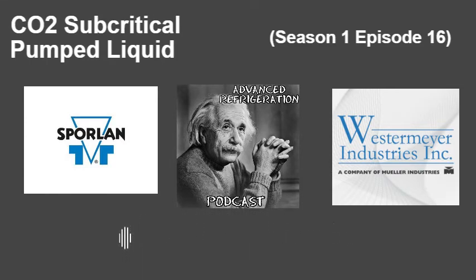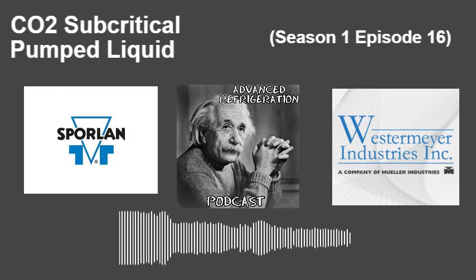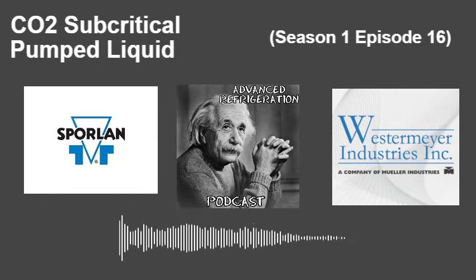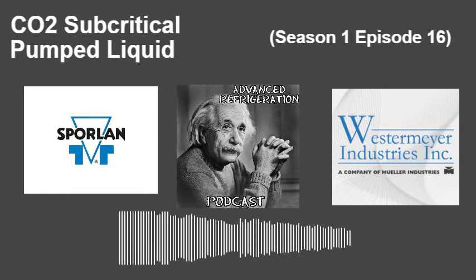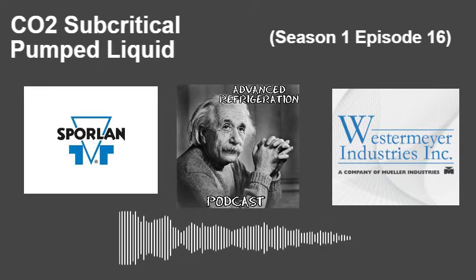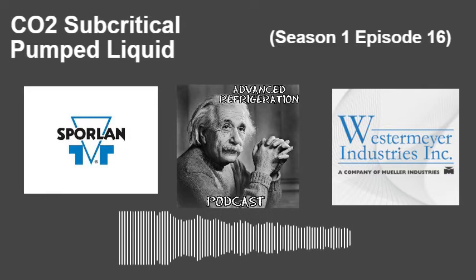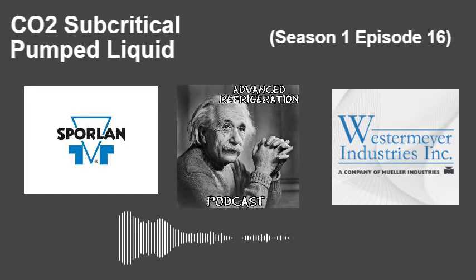So as this liquid's getting pumped around the store, we have a really easy control strategy for this. We have our display cases, and we have our lines coming down that are getting the pumped liquid CO2 through them at like a 10 to 15 pound higher differential. So it's going down through the cases. Now it's going to hit a supply solenoid.